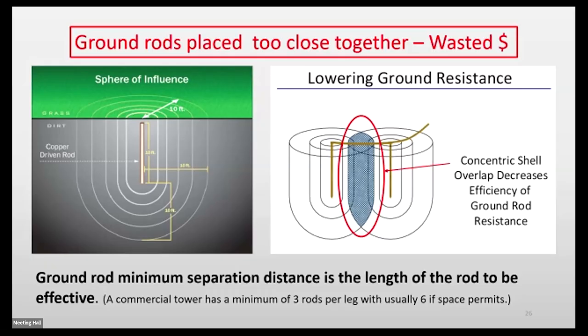They say in the manuals 6 feet apart minimum, but everybody I've talked to, the expertise in this, always said whatever length rod you put in, you go out that same distance. A 10-foot rod, go out 10 feet; an 8-foot rod, go out 8 feet minimum. Beyond that doesn't do you any good for maximum grounding.